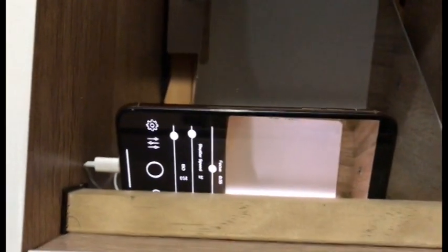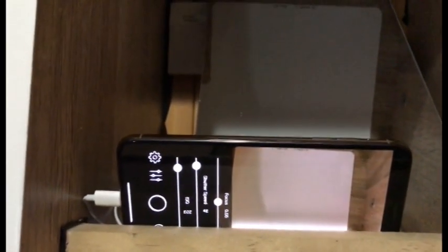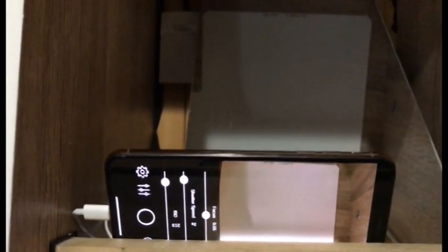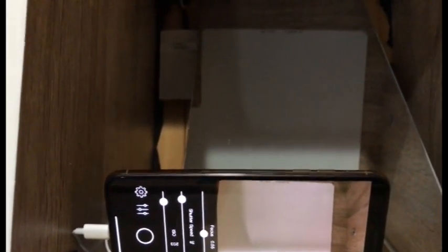It's so much more energy than it's expecting to receive, which results in a really high-powered white dot. If you expose it to that for too long, it will destroy the CCD, or at least damage it. So that's the reason that that mirror is tilted 45 degrees. It doesn't stop all the radiation from hitting the CCD, but it stops quite a bit of it.